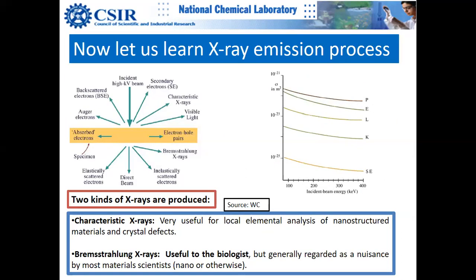X-ray emission: there are two kinds. One comes from your elemental characteristic X-rays — the result of a core electron being kicked out, and then an electron from a higher orbit jumps down to fill the vacancy. In this process, X-rays are emitted carrying information about the element they belong to. Then there are Bremsstrahlung X-rays, which are useful to biologists but are considered a nuisance by material scientists.